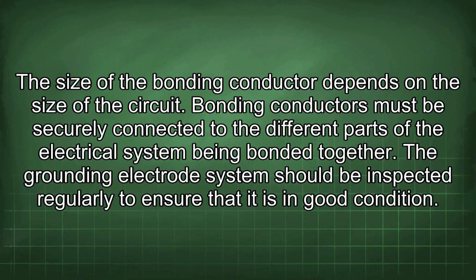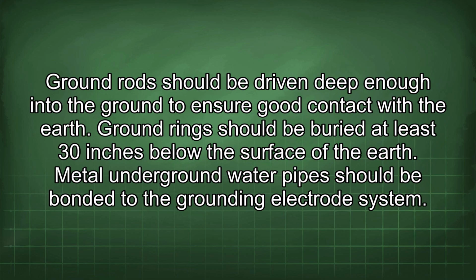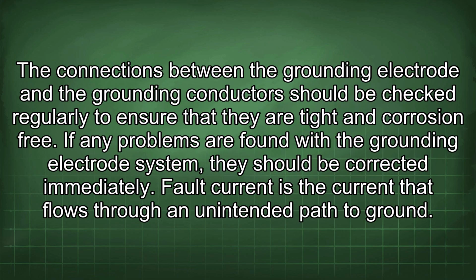The grounding electrode system should be inspected regularly to ensure that it is in good condition. Ground rods should be driven deep enough into the ground to ensure good contact with the earth. Ground rings should be buried at least 30 inches below the surface of the earth. Metal underground water pipe should be bonded to the grounding electrode system. The connections between the grounding electrode and the grounding conductors should be checked regularly to ensure that they are tight and corrosion-free. If any problems are found with the grounding electrode system, they should be corrected immediately.